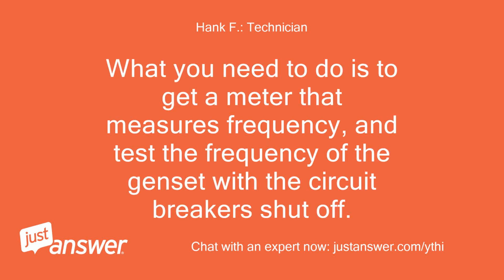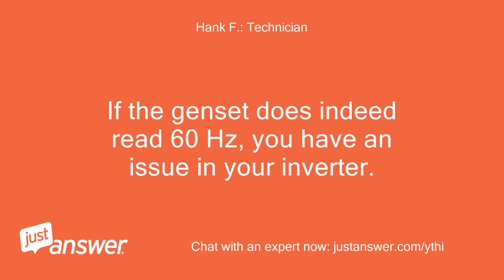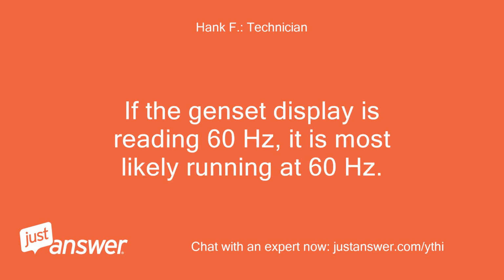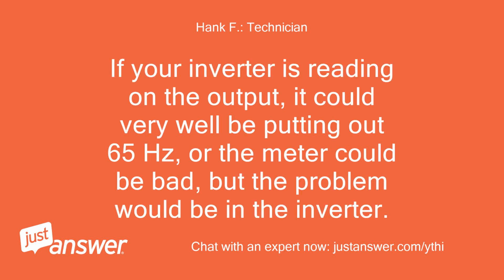What you need to do is to get a meter that measures frequency, and test the frequency of the genset with the circuit breaker shut off. If the genset does indeed read 60 Hz, you have an issue in your inverter. If the genset display is reading 60 Hz, it is most likely running at 60 Hz. If your inverter is reading on the output, it could very well be putting out 65 Hz, or the meter could be bad, but the problem would be in the inverter.